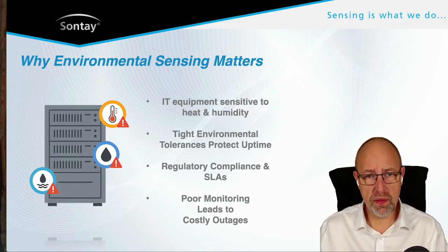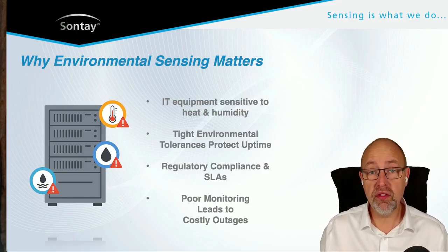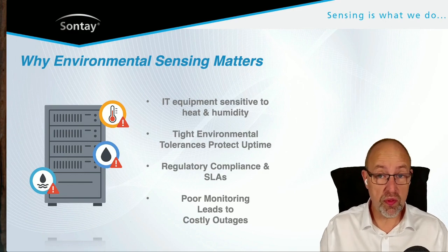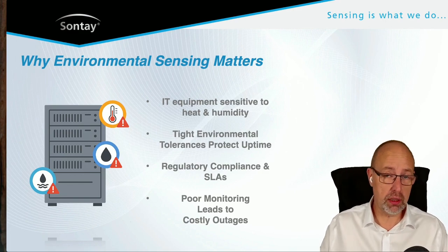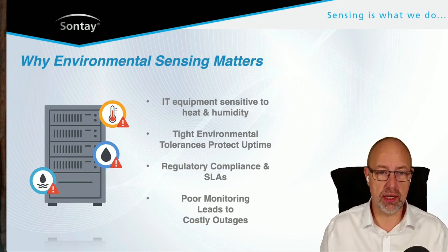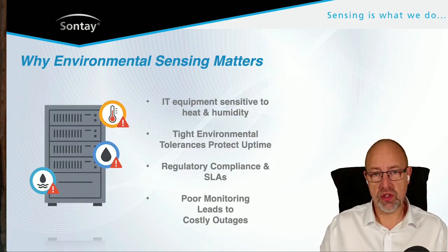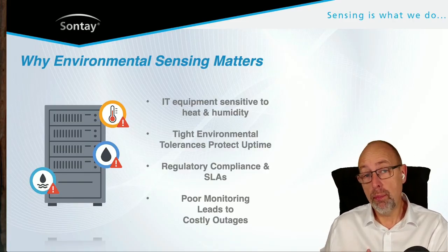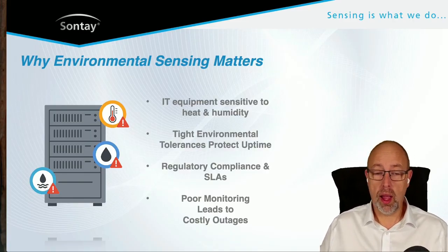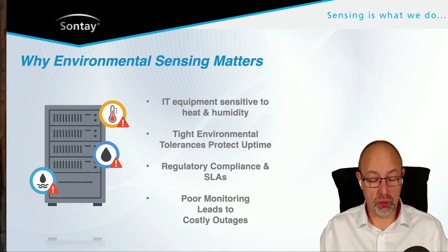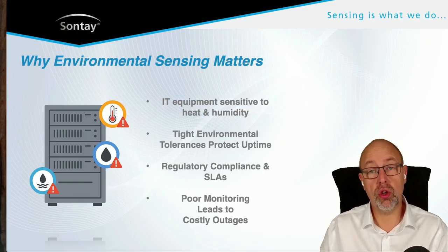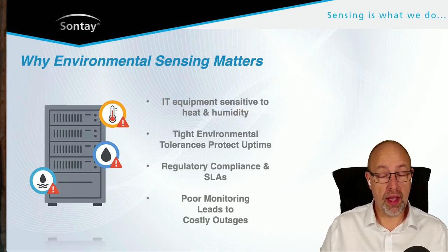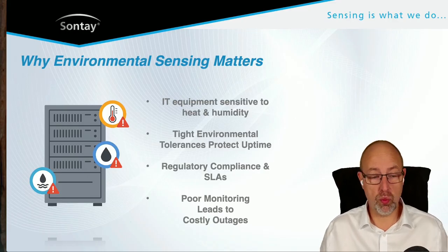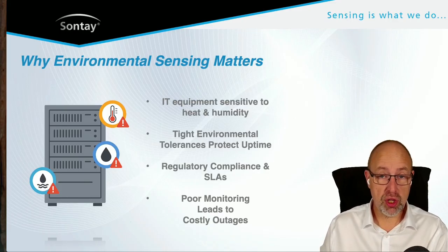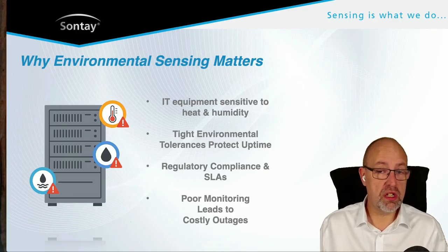There are other things with data centers as well, away from the data halls themselves. We think a lot about airside control in data centers, and rightly so, because that's where all the servers and equipment are. But we also have to think about how that is cooled. You've got chillers, cooling towers, and a water distribution system moving water around that needs to be temperature controlled, and the flow needs to be controlled as well.